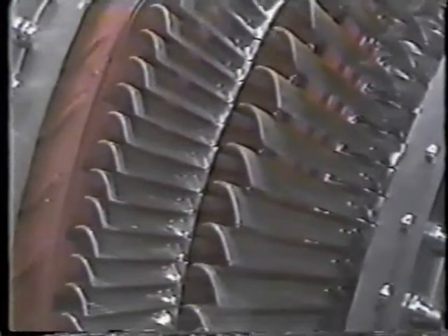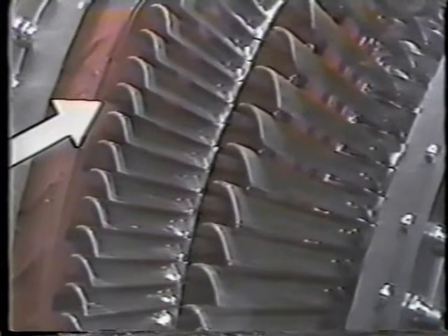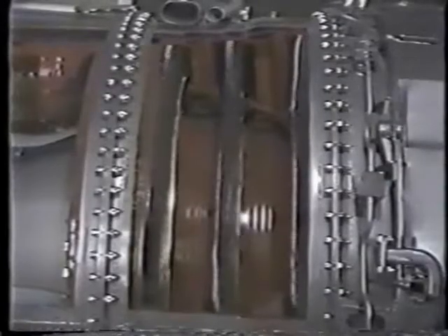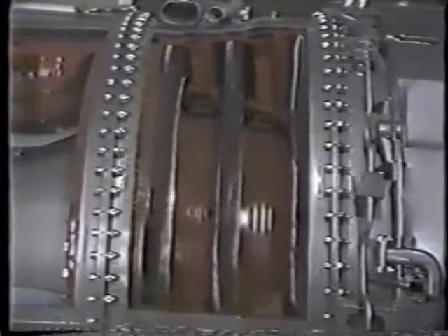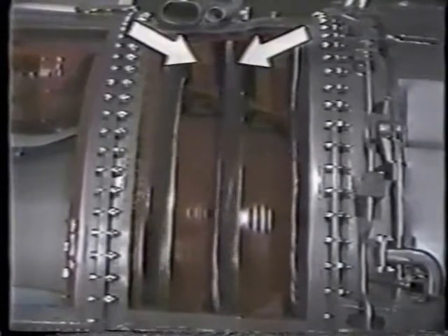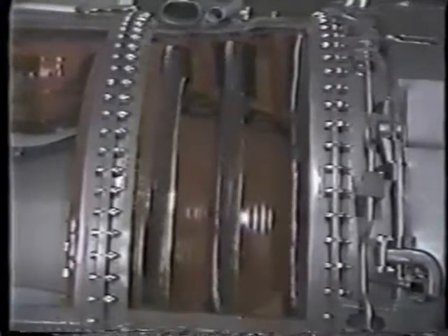Combustion gas passes into the turbine through a set of stationary blades called nozzle guide vanes. The nozzle guide vanes, or just nozzles, direct the gas into the rotor blades at a fixed angle. Gas turbines generally have either 1, 2, or 3 sets of blades. Each set of rotor and stator blades is called a stage, just like in the compressor.